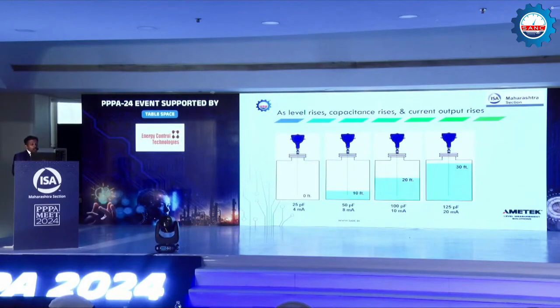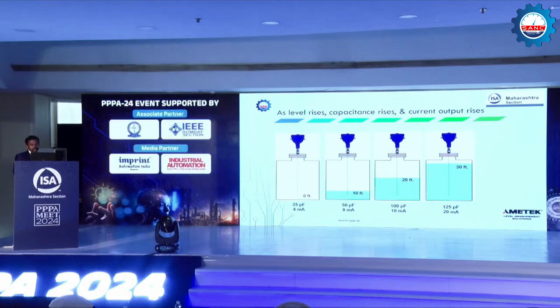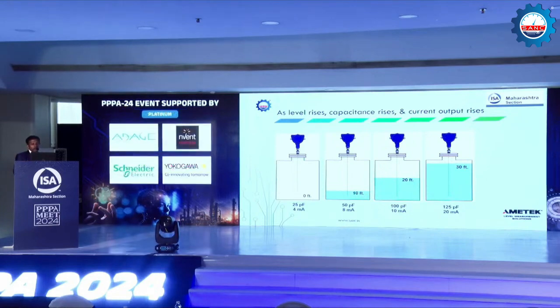As the water level rises, the output capacitance that we are measuring through the transmitter also rises. So at full level, when you reach the top, at 30 feet, you get 125 picofarad, and that becomes the span. This is as simple as that. So this is how it is calibrated.